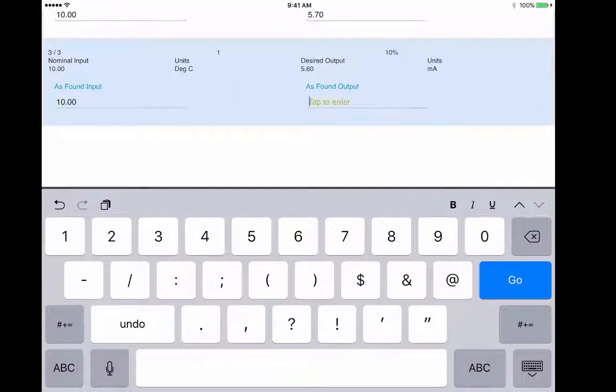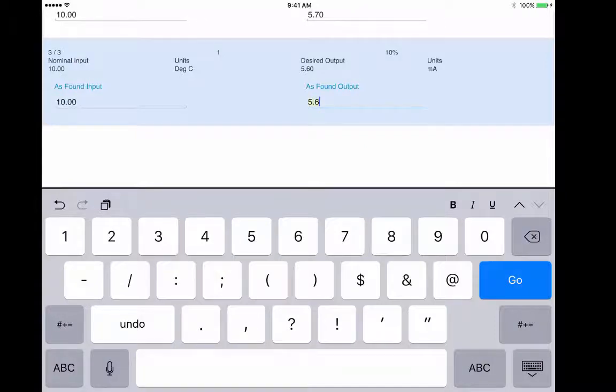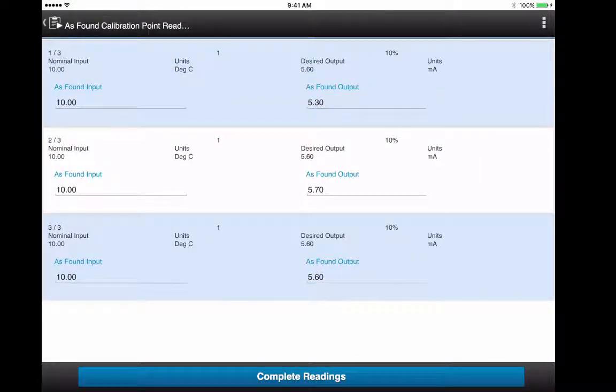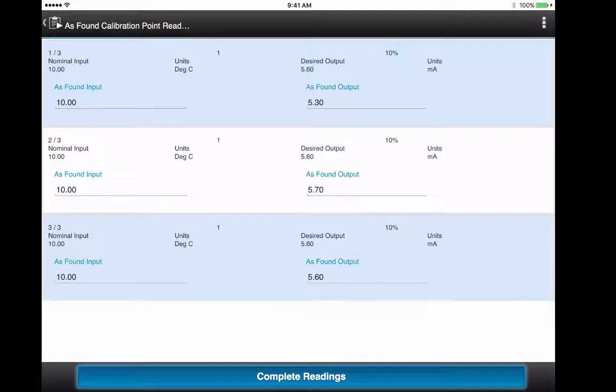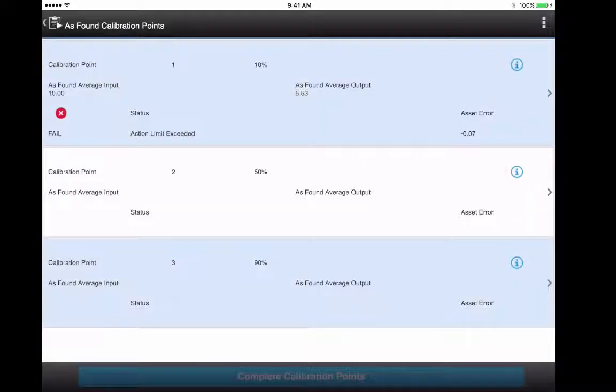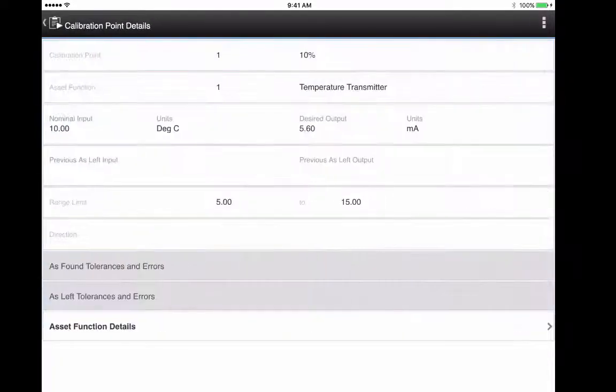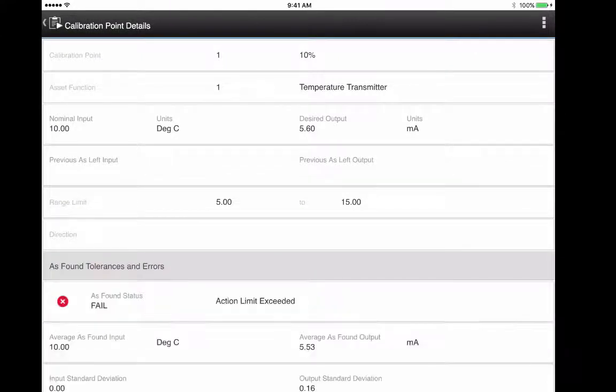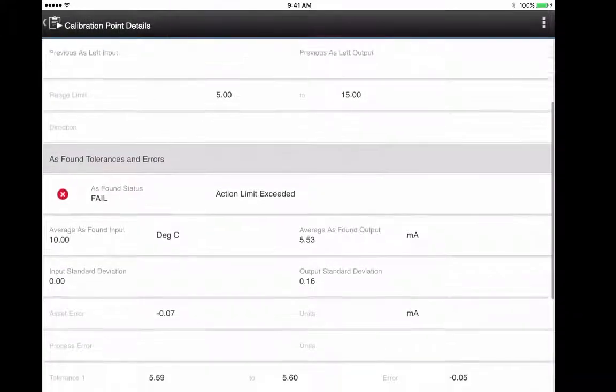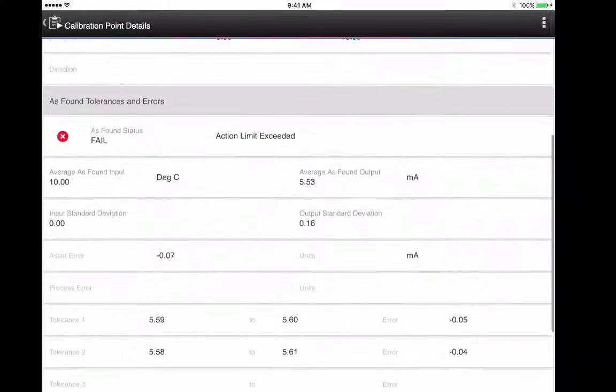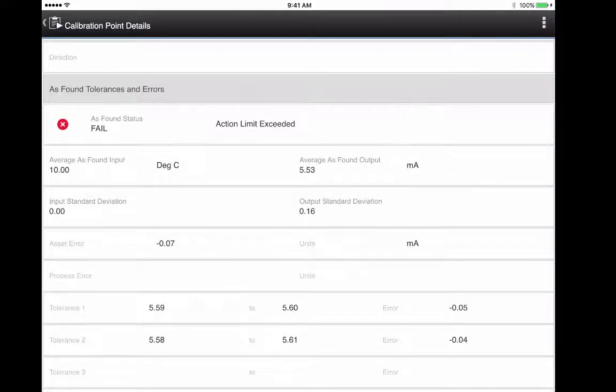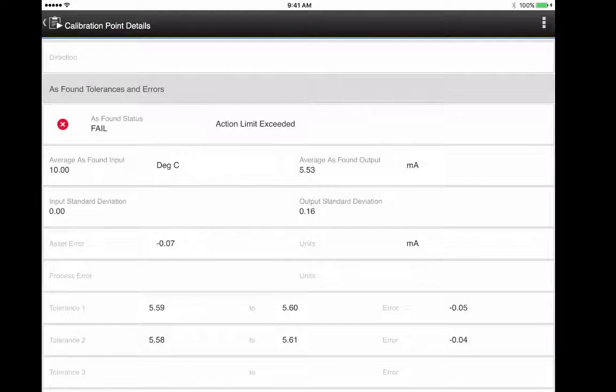After all the data has been captured, it calculates the status based on the average. In this case, it has failed. They can tap on the icon to see more information. Notice the average as found output and input, and also the standard deviation, which is also a calculation captured.